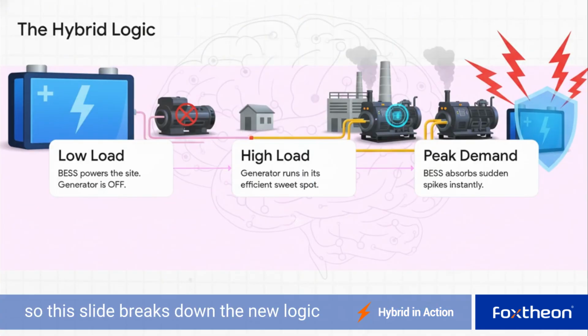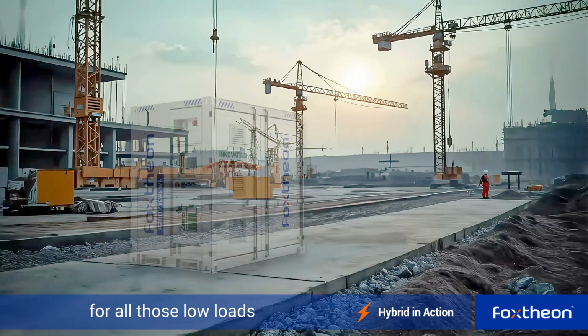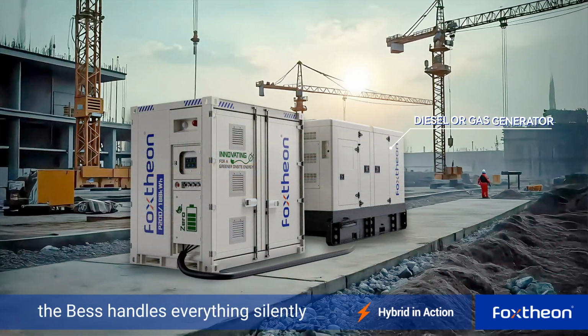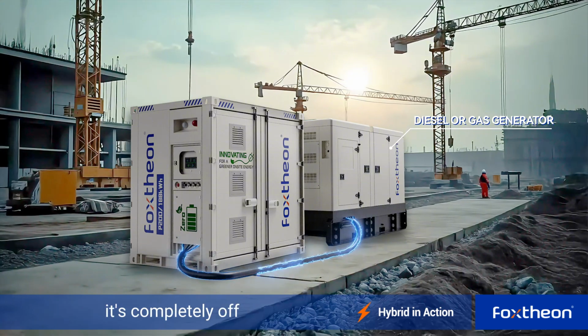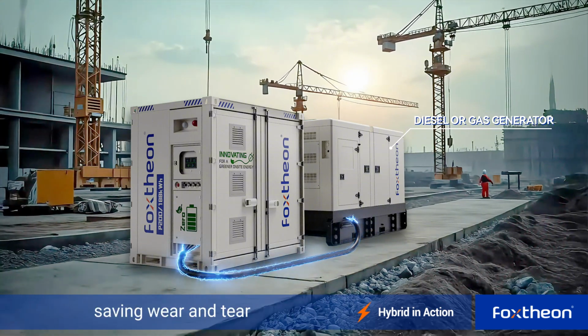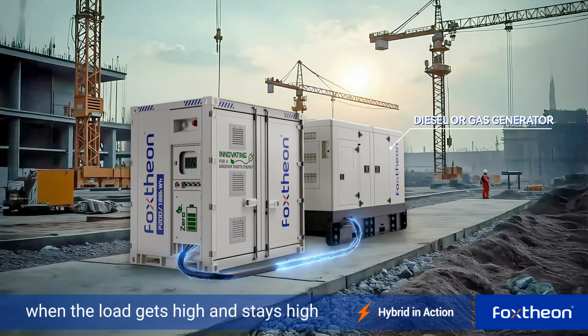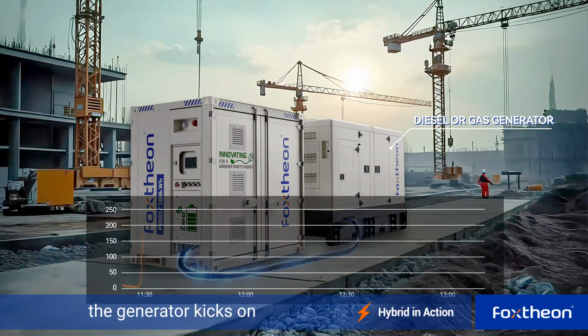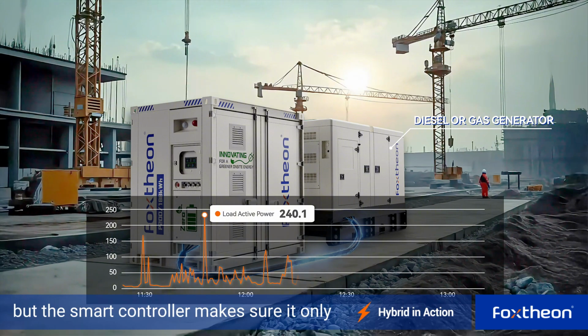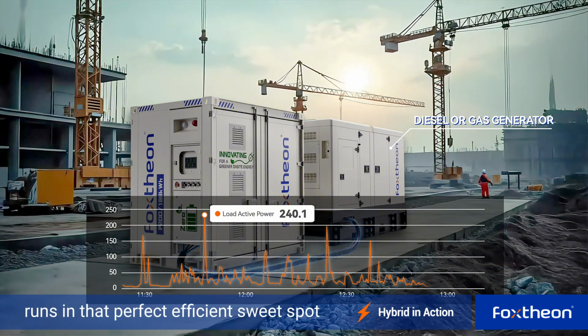This slide breaks down the new logic. Let's walk through it. First, for all those low loads, the BESS handles everything silently, the generator is completely off, saving fuel and wear and tear. Now, when the load gets high and stays high, the generator kicks on, but the smart controller makes sure it only runs in that perfect, efficient sweet spot.